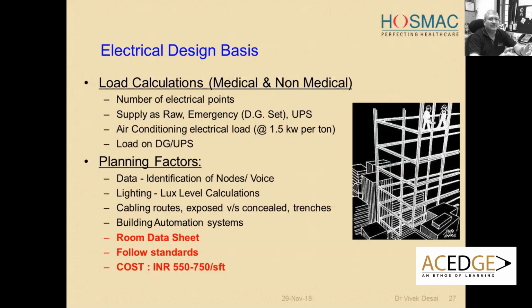So now suppose if I do a room data sheet for an intensive care cubicle, because it's a life-saving kind of area, when I say supply as raw, emergency or UPS, then I will need to do those plug points with UPS, because anytime, in a life support, a ventilator used for artificial breathing cannot go shut. You cannot have an operation theater where while you are doing an operation the lights go off - that will need to be backed by UPS. You cannot have a blood bank refrigerator without power, so that needs a UPS - that 30 seconds, 1 minute on UPS, and then the DG kicks off. This is important for us, since we are, like I said, a 365-day kind of a system.